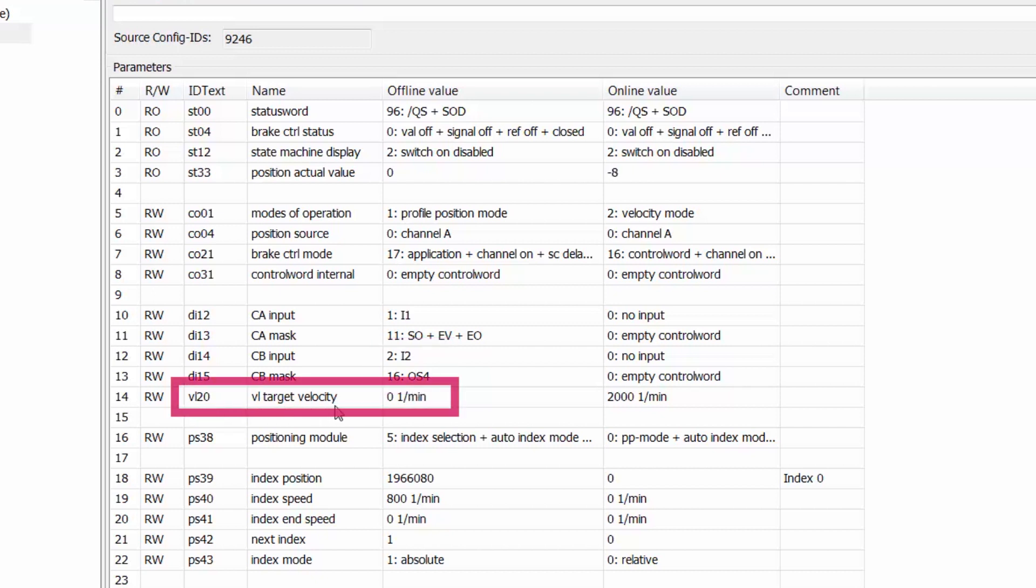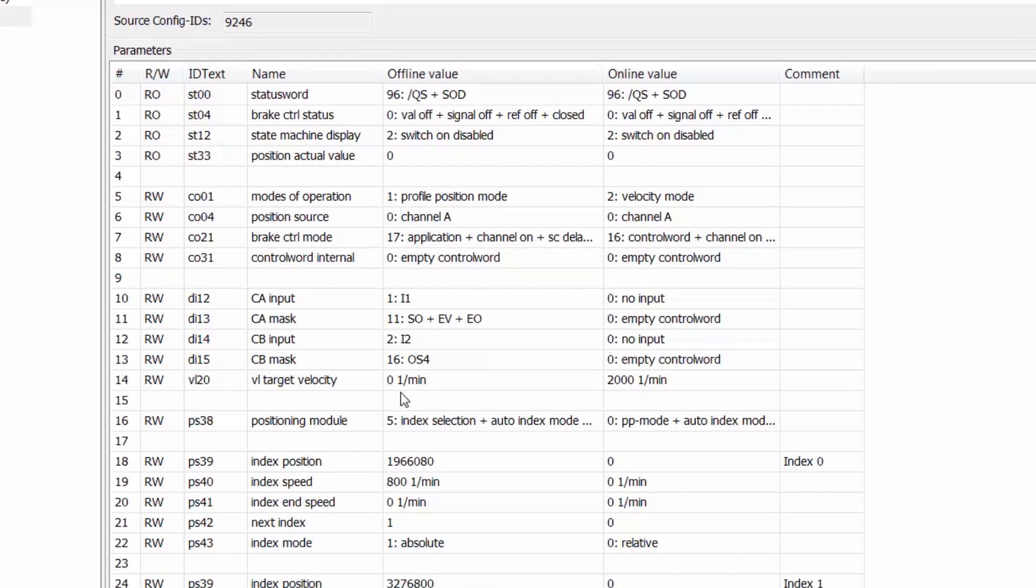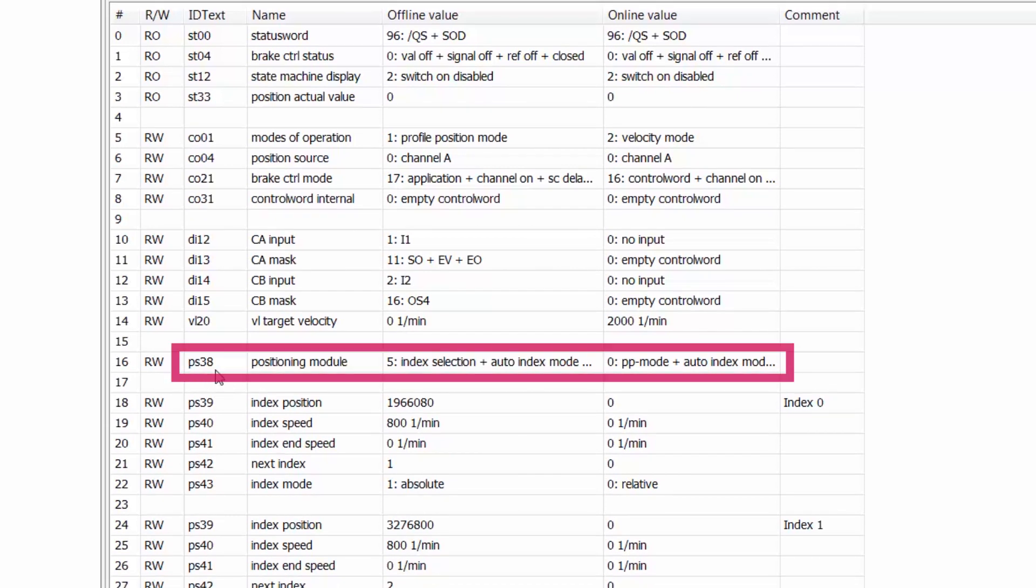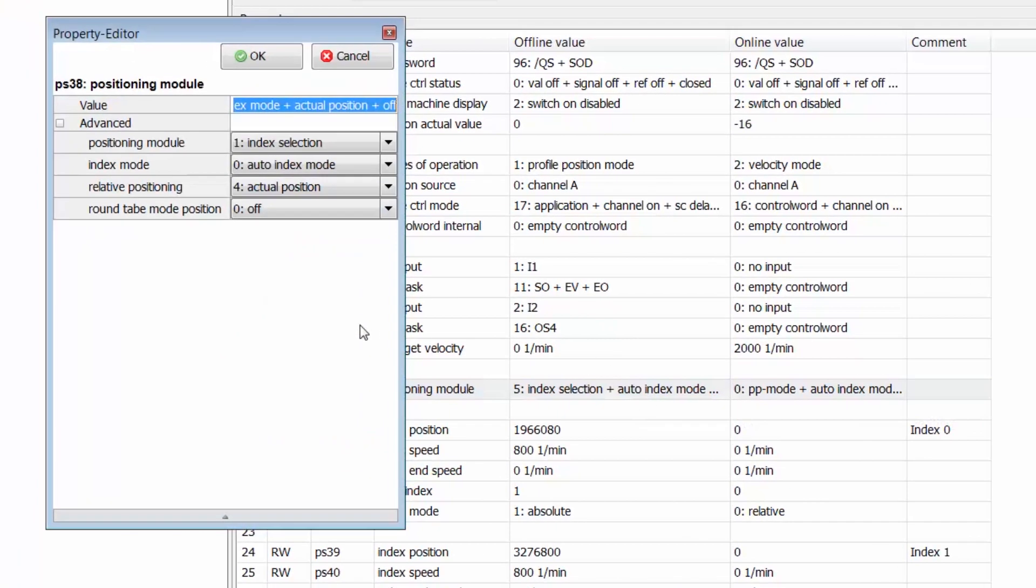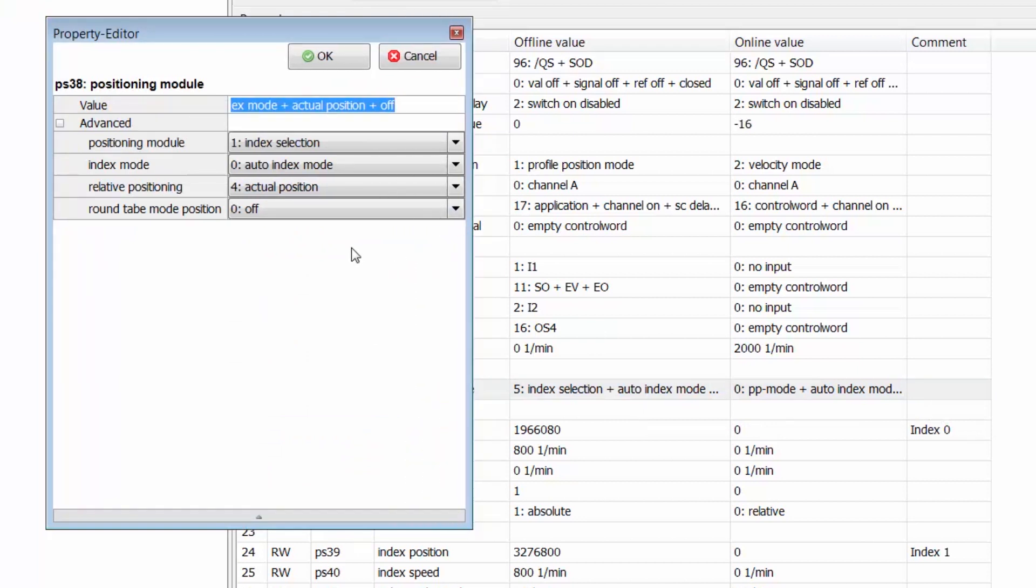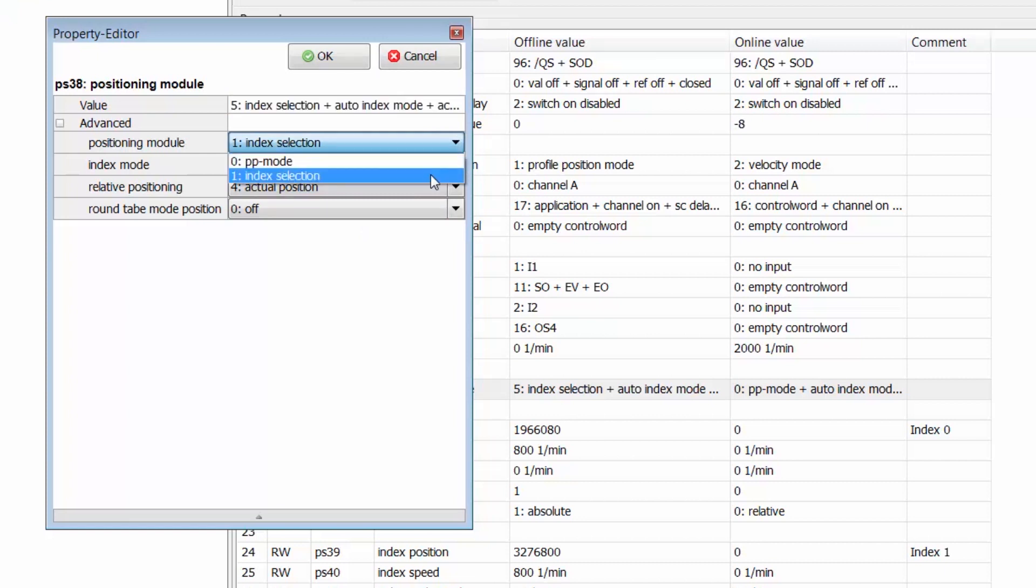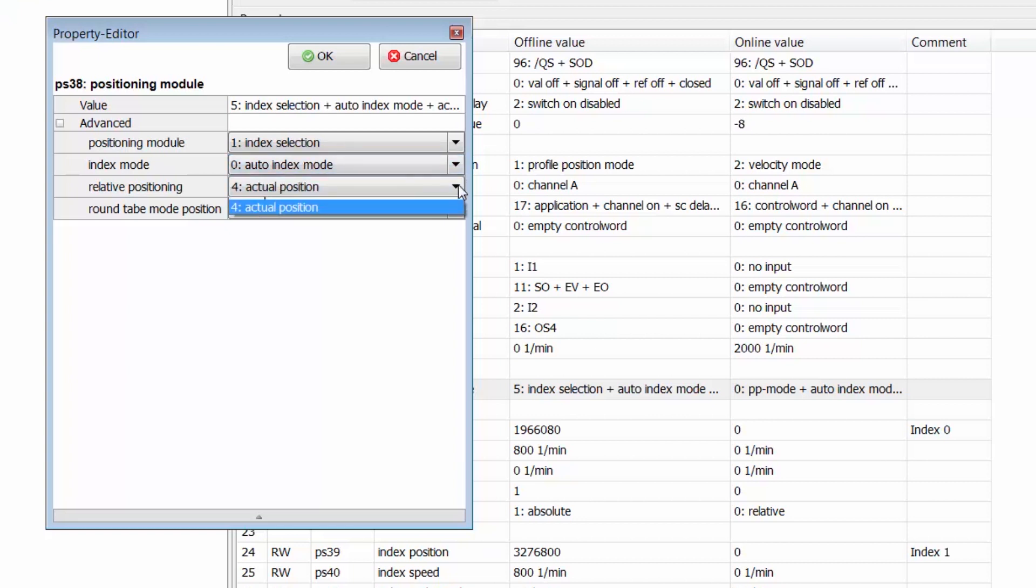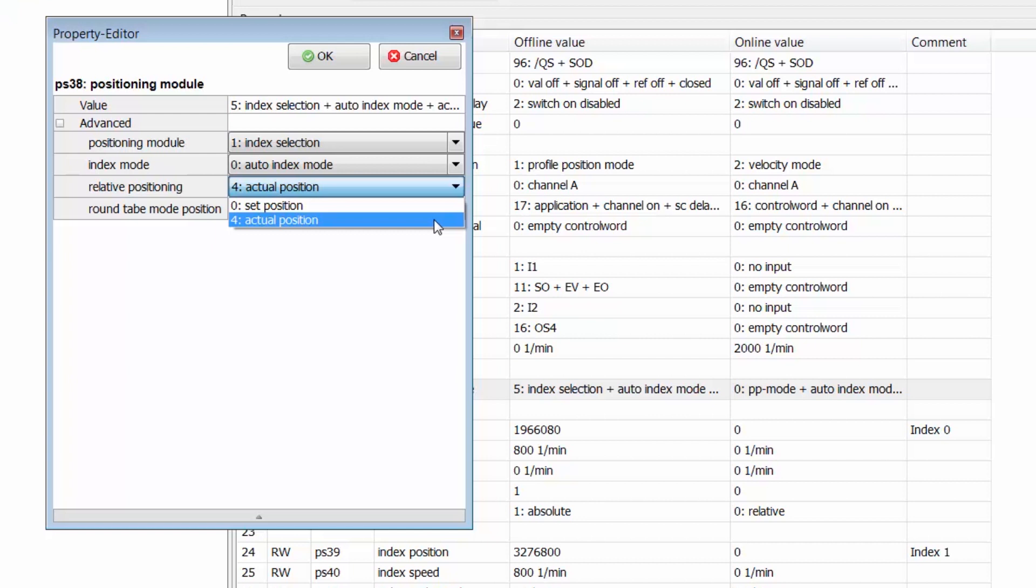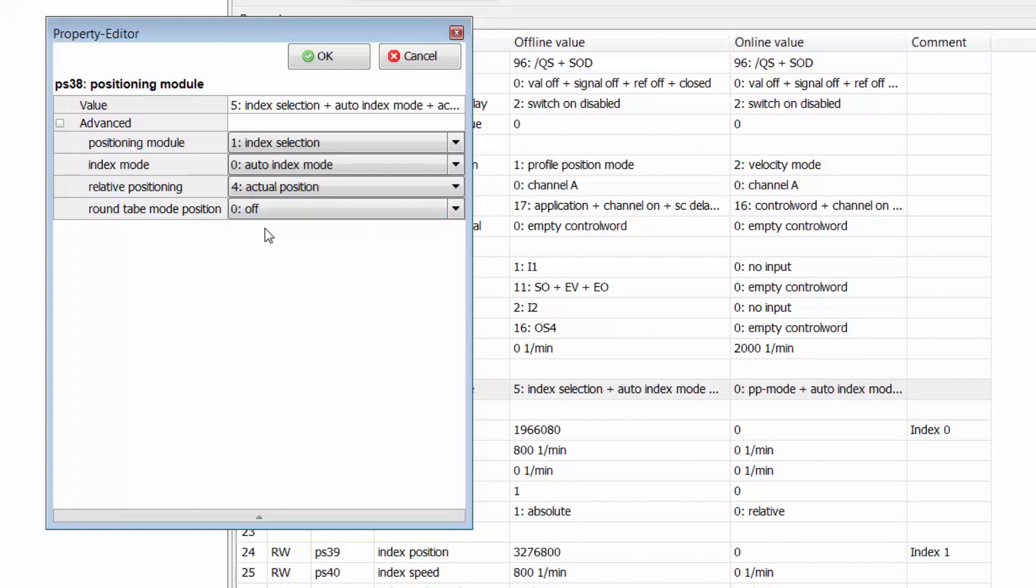VL20 is our target velocity parameter. We are going to set that to zero RPM so that when the drive is not actively positioning it will hold at a zero speed position and not rotate continuously. Parameter PS38 positioning module is really important in this application as this sets the positioning module for the drive. So just opening up this parameter we can see the options we have for this positioning module. So for the positioning module we will select index selection which will allow us to utilize our 32 indexable positioning points. Our indexing mode is auto indexing mode and we also have stop after each index if desired. For relative positioning you can either choose to perform relative positioning based on the set position that you have or the actual position that is being measured at the encoder. For our sake just for this test we'll use the actual position and you can also use roundtable positioning mode but we will have that off since we won't be using roundtable positioning in this case but that is an option for you if you so desire.